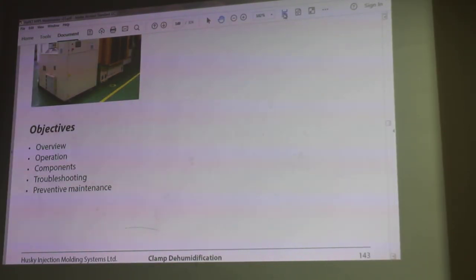So if these surfaces are very cold, we need to be sure that the dew point in the air around the mold has a dew point lower than the temperature of the mold. If the temperature of the mold is 10 degrees, we need to be sure that the dew point in this mold enclosure should be 5 degrees lower than the temperature of the mold.